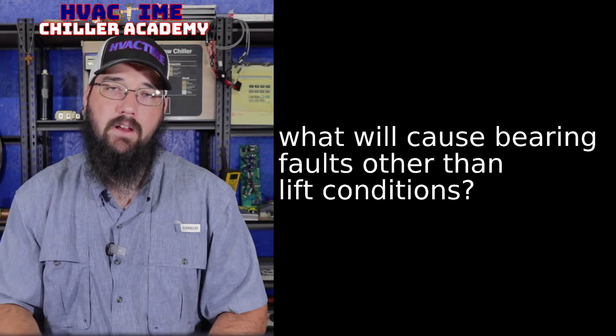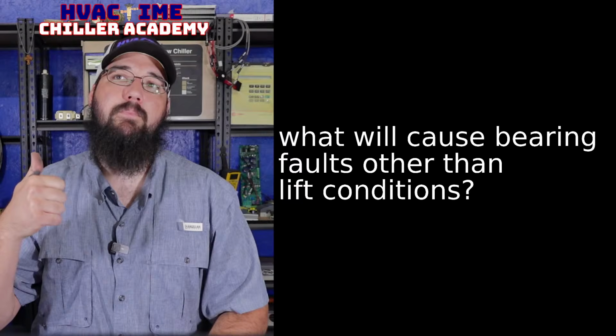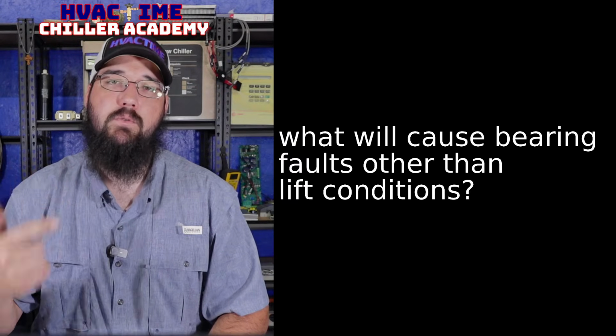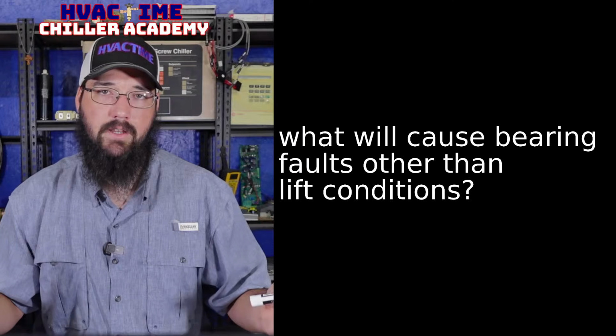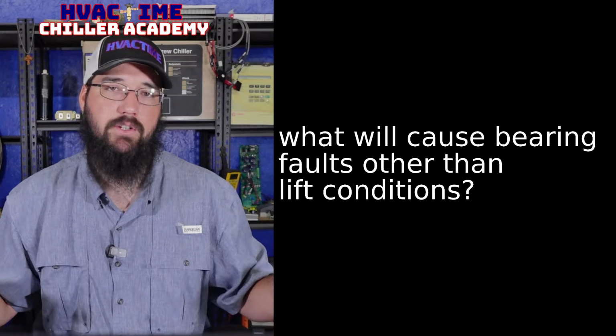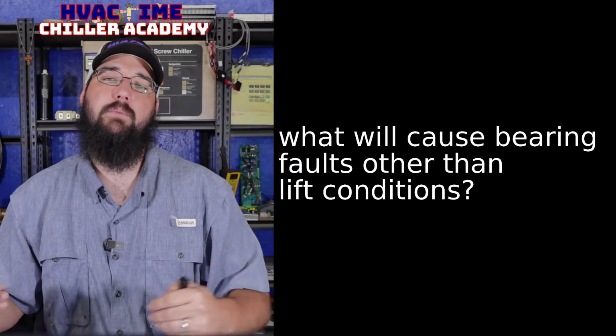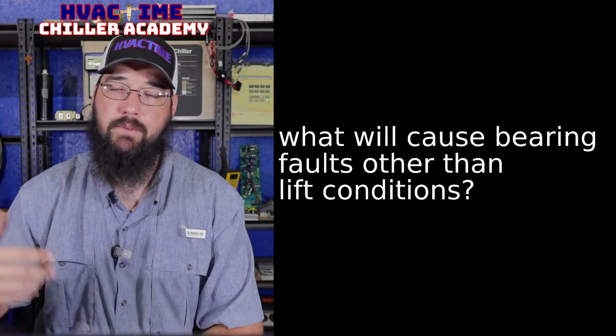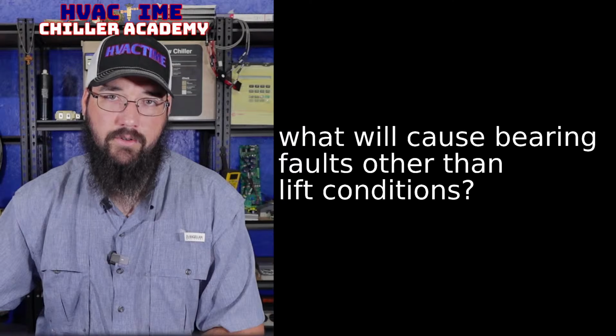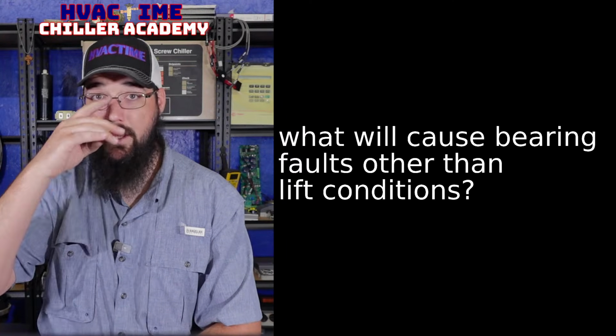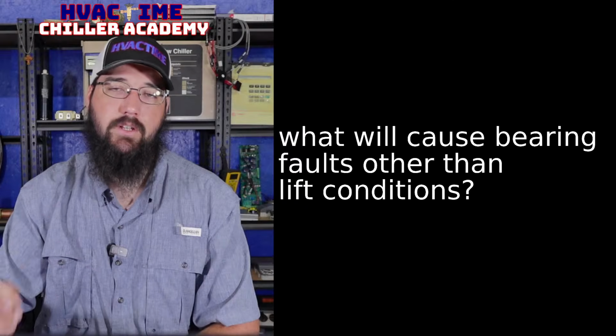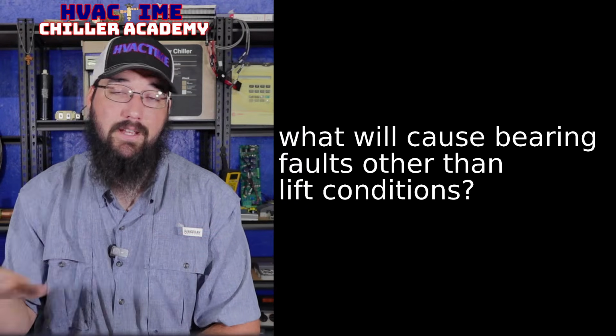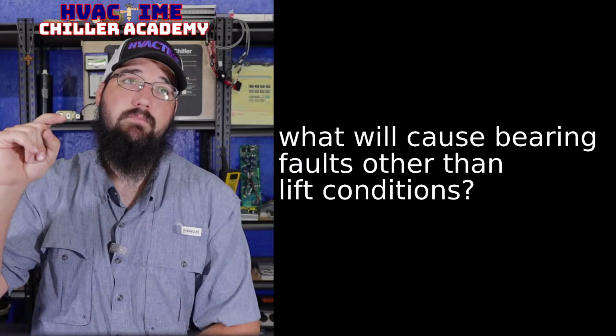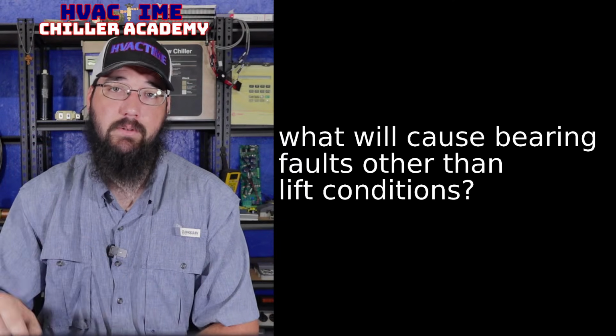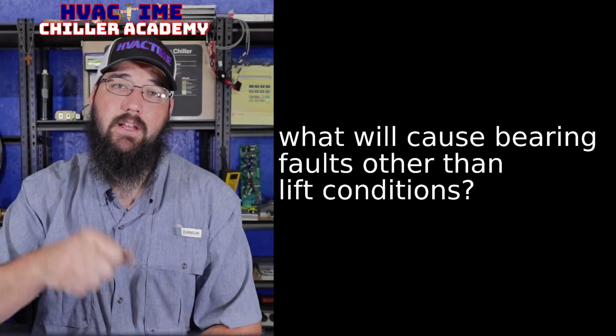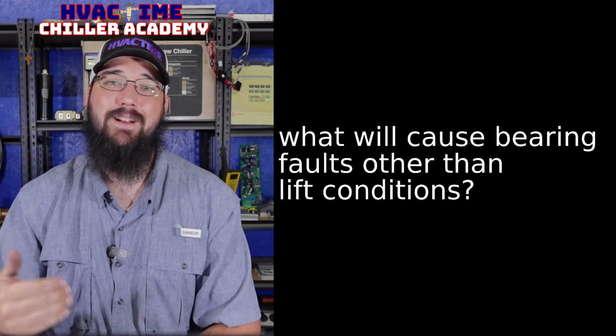So if you don't have a lift problem and you're not having an actual bearing issue, where your bearings test fine, the sensors test fine, everything checks out perfectly on the bearing side of the system, but we're still having bearing faults and we know we don't have a lift problem, the next thing I'm going to check is, okay, is my inverter potentially causing a problem? Now, the inverter could test perfectly good, but still be causing instability. Just because it passes the electrical test you would do with a meter does not mean the inverter is not having a problem.